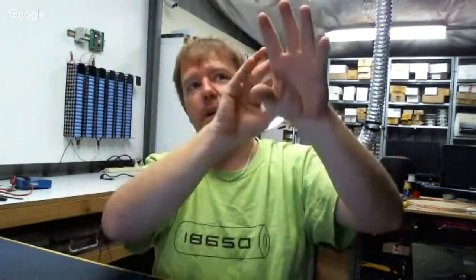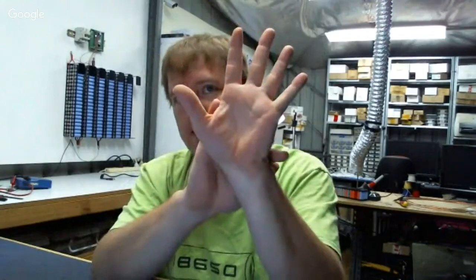So basically, I go from my normal switchboard here, it gets interrupted. The power comes into a 63 amp 4-pole changeover switch or generator switch, and then 1 pole goes back to these circuits and completely bypasses all the grid, the off-grid. When I pull the breaker down or the transfer switch, it switches to off-grid or bypass mode, so it goes from the grid through the inverter, back up through those circuits again. So it's properly fused all the time. And if the inverter runs out of battery power, it automatically switches back to grid and you don't even notice it. I think that makes sense.